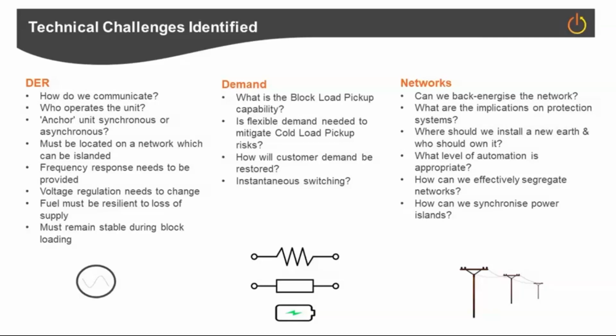On the demand side, the flip side, there's block load pickup. These are the chunks of demand that a generator has to be able to pick up to load up to a stable load, and that's applied in blocks. So what's that block load capability, and the demand? Do we need some sort of flexible demand in order to stabilize that generator?